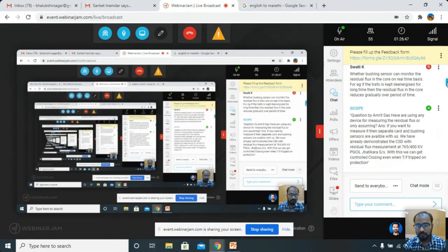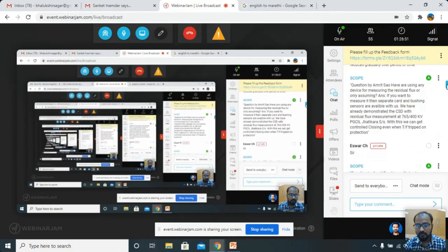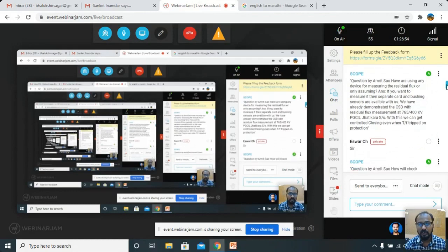What is the acceptable voltage level at which these bushing sensors can be used? We have the bushing sensor up to the 765 kV system, sir. Correct. So naturally, on the higher voltage side, you require them. Is there anything you would like to say about going down towards the lower voltage levels, whether it is usable only beyond a certain voltage level? Nothing like that, sir. With the bushing sensor, we have the results with every operation. We are sure on that.